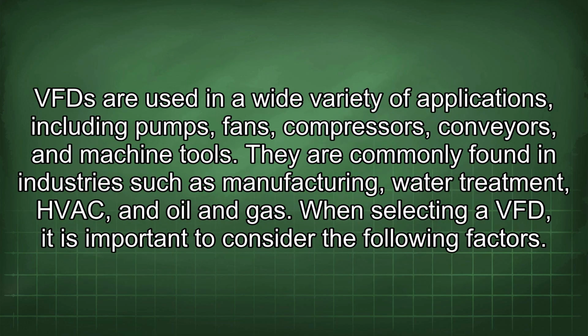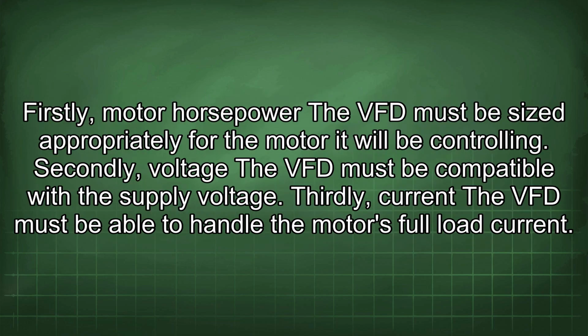VFDs are used in a wide variety of applications, including pumps, fans, compressors, conveyors, and machine tools. They are commonly found in industries such as manufacturing, water treatment, HVAC, and oil and gas. When selecting a VFD, it is important to consider the following factors. Firstly, motor horsepower. The VFD must be sized appropriately for the motor it will be controlling.